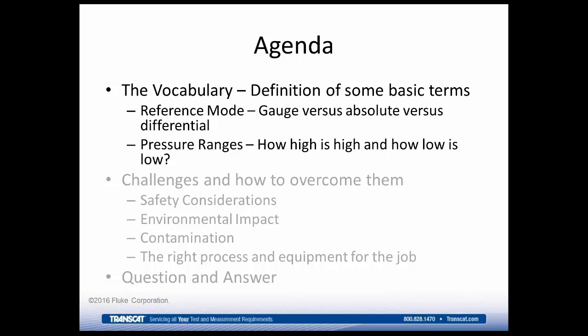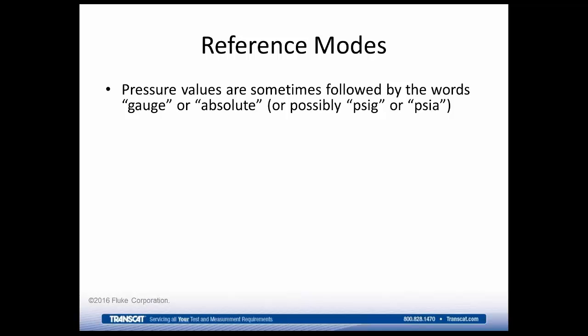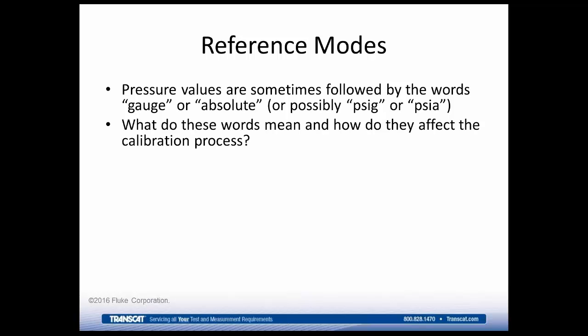So let's move first into the vocabulary. And the first subject that we're going to cover is what's called reference modes. You'll often see pressure values followed by certain words like gauge or absolute. You could also see it truncated or shortened to say PSIG or PSIA. And the question is, well, what exactly does this gauge or absolute mean? What is a PSIG and what's a PSIA, and are they different from each other? And how does that affect our calibration process? What do we have to do differently if the pressures in question are gauge versus absolute?